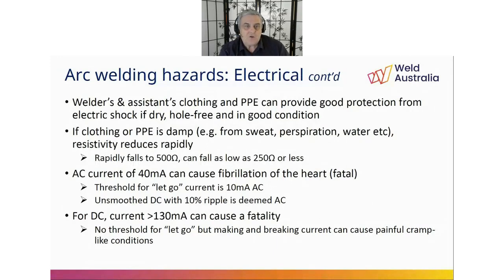Now, for those who aren't electrically savvy, at 20 volts AC, a 500 ohm resistance will cause 40 milliamp to flow. Depending on the current path, this can cause a fatality because it's sufficient to cause heart fibrillation. At 65 volt DC, which is quite common in some older machines on an open circuit voltage or even higher, at 500 ohms, that will cause 130 milliamp to flow.